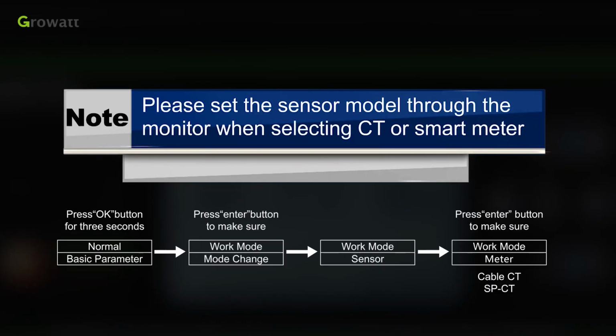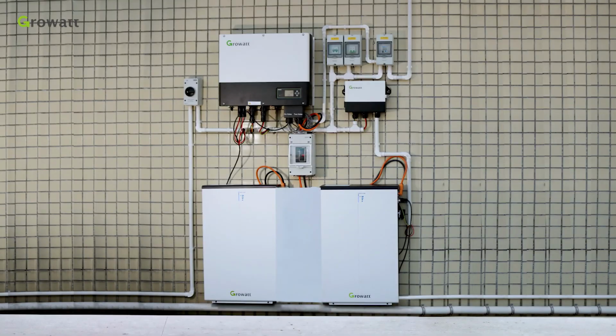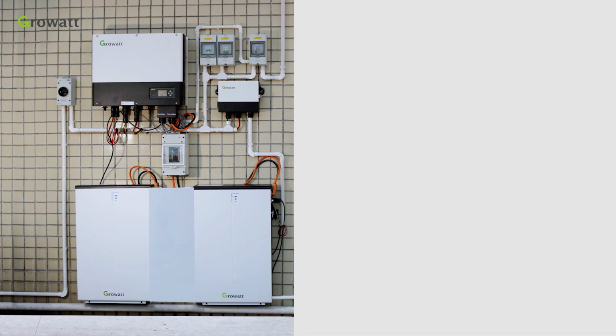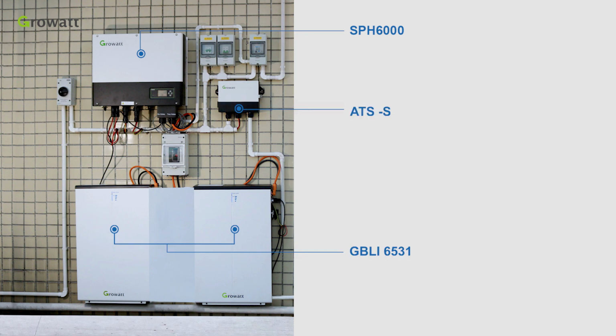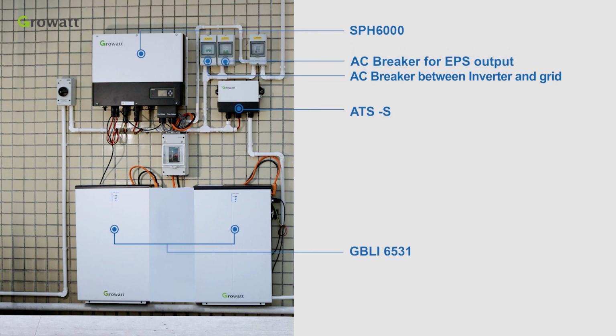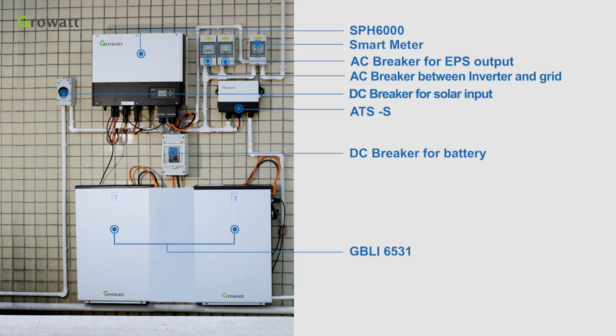Note: please set the sensor model through the HMI when selecting CT or smart meter. Here is the final energy storage system including SPH 6000, GBLI 6531, ATSS, AC breaker between inverter and grid, AC breaker for EPS output, smart meter, DC breaker for battery, DC breaker for solar input.